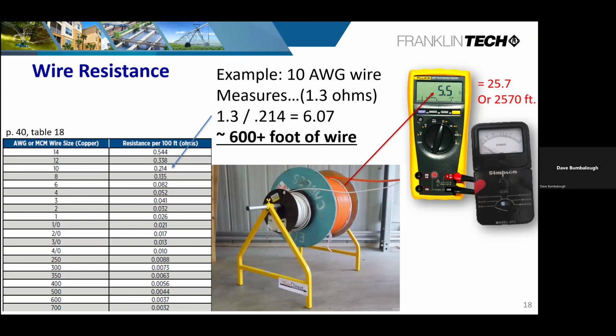And the rule of thumb is that you're checking two conductors. So it has to be at least a 2-wire. If you're checking a single wire, there are other ways of doing that, but you have to have at least 2 wires to test. One end you will wire nut together or connect together somehow, and at the other end you're going to go across it with your ohm meter.